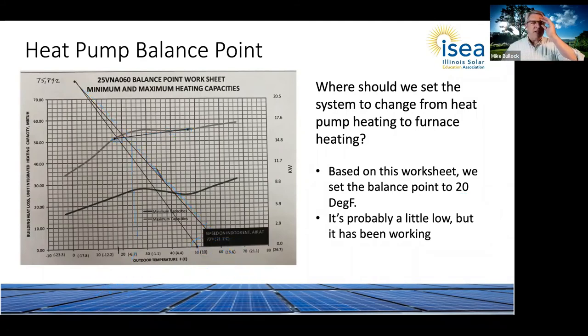So the efficiency - why I went with oversize: because when the heat pump is running here, it's more efficient than when it's running here. If I would have had a 4-ton, instead I went with a 5-ton. If I had the 4-ton, the most I'd be able to get out of it would look something like that curve, which would put the balance point higher than 24 degrees. So I'd be running it less on heat pump, more on the furnace. That's why I wanted to oversize - because I can create more heat at lower temperatures.